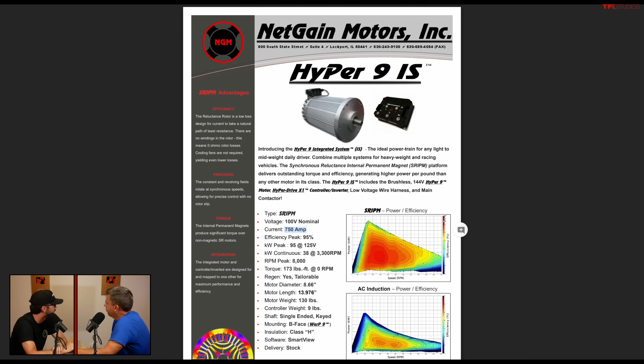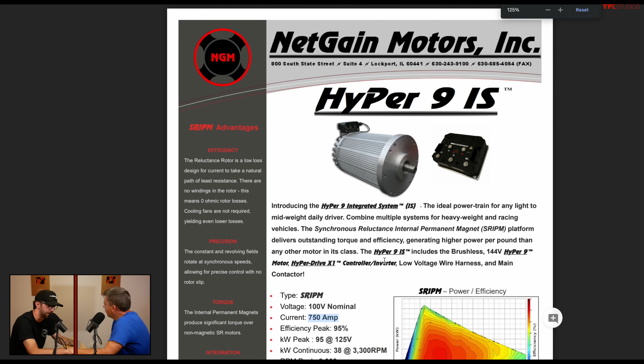And what are those graphs? Is it kind of like an RPM overlay for the power? Yeah, this is power and efficiency. On the left-hand side we've got power in kilowatts, then speed in RPM, rotations per minute, and then color for efficiency. So really what we're looking at is our highest efficiency around — let's zoom in to see this better — I believe this is around 1,500, 2,000, 2,500 RPM on the shaft of the motor, with lower kilowatt output. That's our optimal efficiency speed right there.